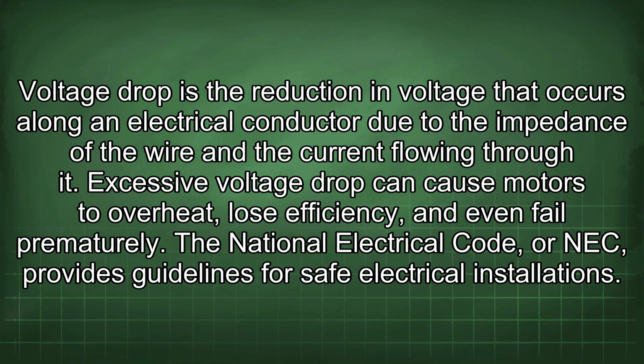Voltage drop is the reduction in voltage that occurs along an electrical conductor due to the impedance of the wire and the current flowing through it. Excessive voltage drop can cause motors to overheat, lose efficiency, and even fail prematurely.